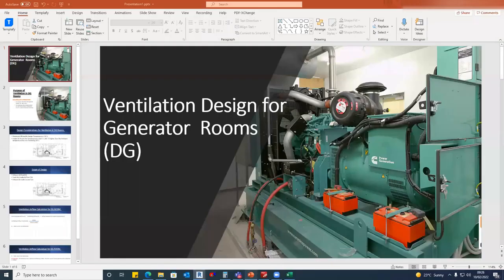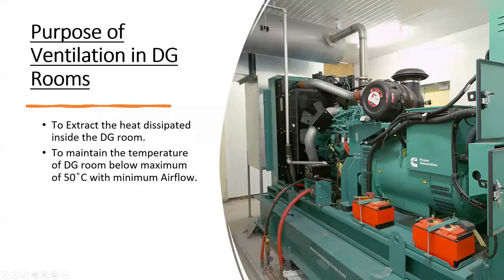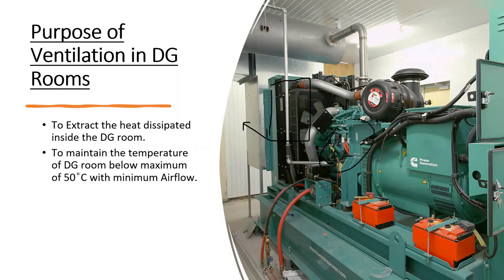Before that, I will go through with the slides. What is the purpose first? Why do we do ventilation? Because we need to extract the heat dissipated from the generator. There are two sources: one is the radiator, which puts out more heat, and second is the engine. These are the two main sources of heat generation. We have to extract this heat with the help of a fan or natural ventilation.